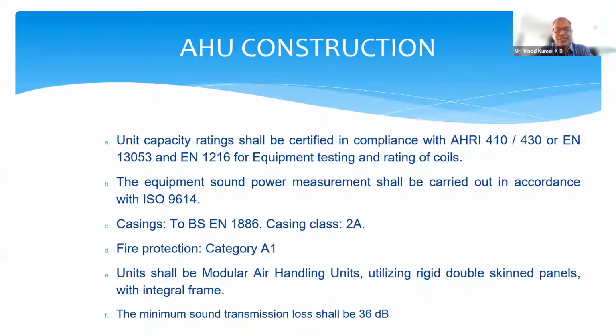So the standard, the unit capacity, then there are various things that we need to look at in the selection of the AHU. These AHUs are being made by various vendors, and each part of the AHU has different ratings and standards that are mandatory. For example, the unit capacity. When I say the capacity of an OT AHU is 10 tons, the capacity has to be calculated and the unit selected according to the AHRI standards or the EN standards, according to the position or the manufacturing facility wherever they are located, or the standards they follow. Some of them follow the British standards, some the European, and some the American standards. So we have to see what standards the manufacturer is following and the capacity. When I say 10 tons, I need to get 10 tons. Is it certified? Yes, the calculations and the selection of the AHU should be certified for it.